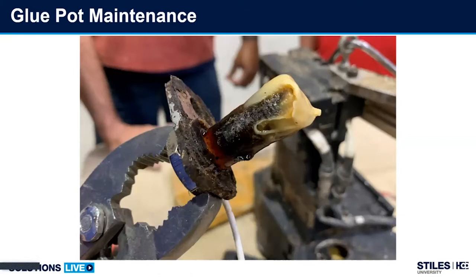In the next slide, we can see this is a customer's probe, very poor maintenance. We can see it's burnt, charred around the probe with a little bit of glue. Luckily this probe was still working, but it wasn't long for this world. It needed to be cleaned or replaced. Frankly, the customer got it replaced after this photo, but it needs to be maintained. It'll never get to this point if proper maintenance is performed.